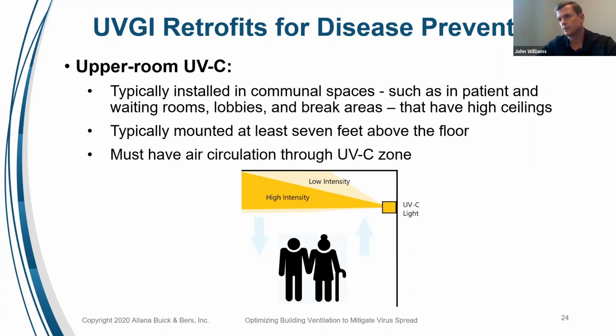I'm thinking of, say, a hotel ballroom, where you have a massive ceiling plenum with high volume but low velocity, and potentially putting UVC lights above the ceiling there. If it's a big open area, we could potentially get the intensity and the exposure duration we're looking for. I guess what you're saying is that you make sure it's carefully engineered and thought through and put in the right place so that it has the impact you're looking for, not just stick a light up at the ceiling and expect it to work.